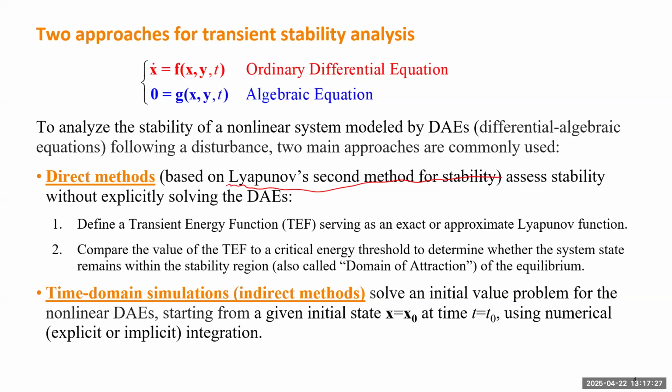stable or unstable. If you see most variables have a very clear trend going back to the equilibrium or static condition, it means the system is stable. If any variable is flying away, you can stop there. You can give a judgment of transient instability.